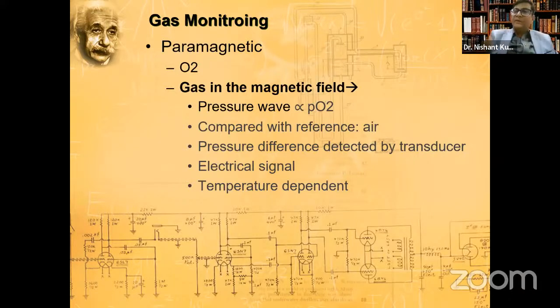And when a sample gas passes through it, a magnetic field is produced, which produces an electrical signal, and the strength of the electrical signal is proportional to the amount of oxygen present. So that is how we get the FiO2 and end-tidal oxygen from this paramagnetic sensor. Now, since it's a magnetic field and an electric current is provided, the magnet does not wear off. So it gives a very good long-lasting life, but it is costlier and it is essentially temperature dependent. So there's a heater there and a particular temperature is maintained in the case where the paramagnetic sensor is kept.